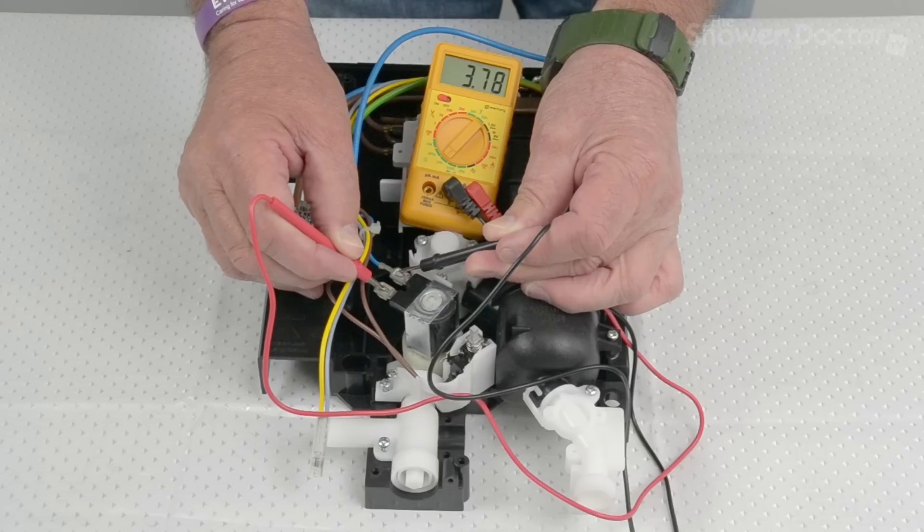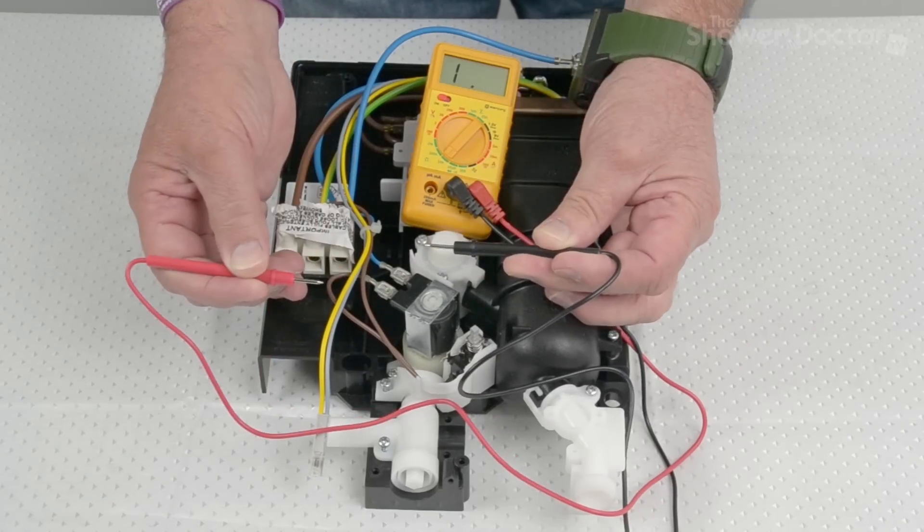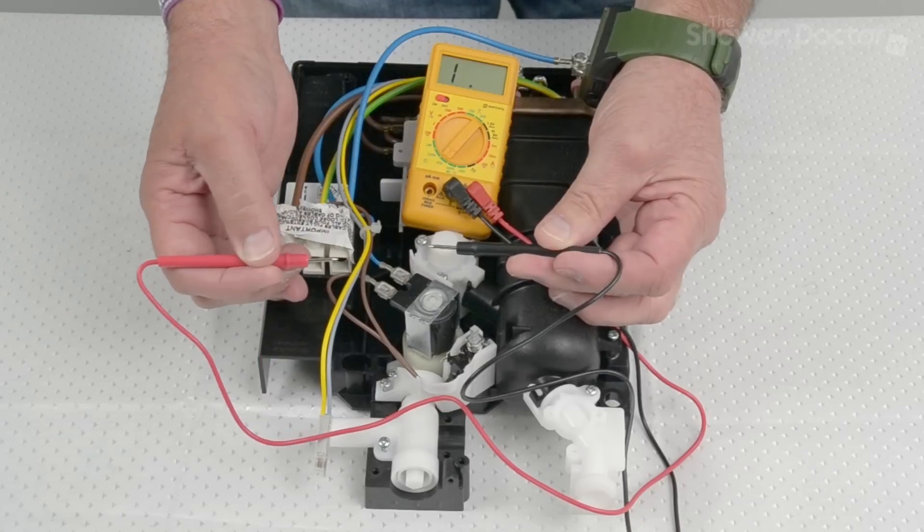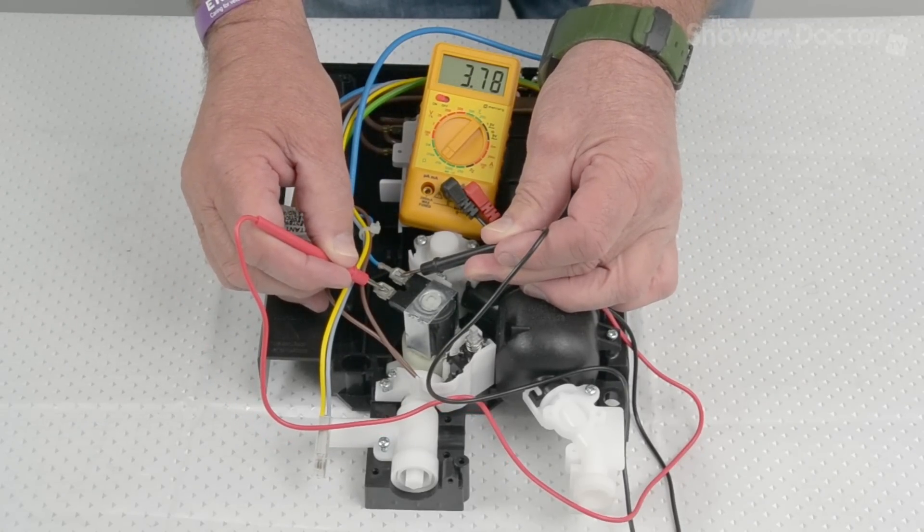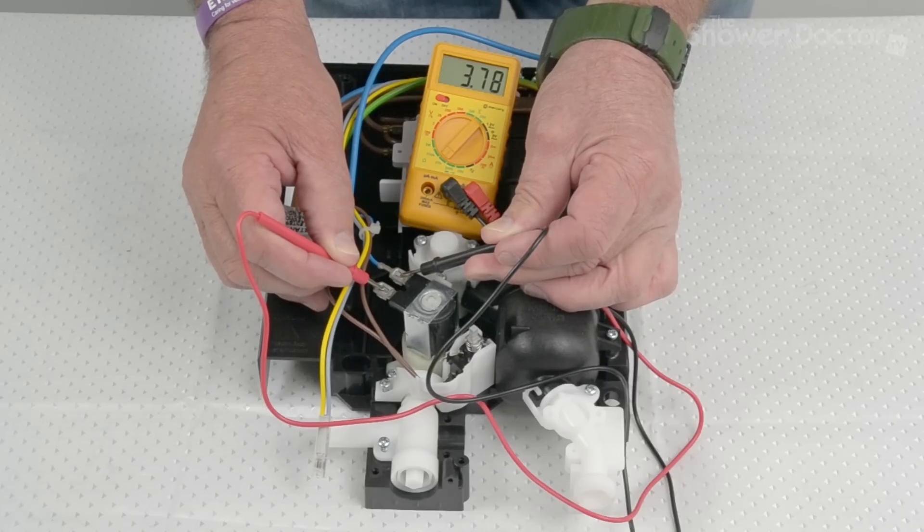Anything less than that, the solenoid is faulty. So often you'll get a zero reading on the solenoid if it's faulty. But normally anything less than 3.4 and the solenoid needs replaced.